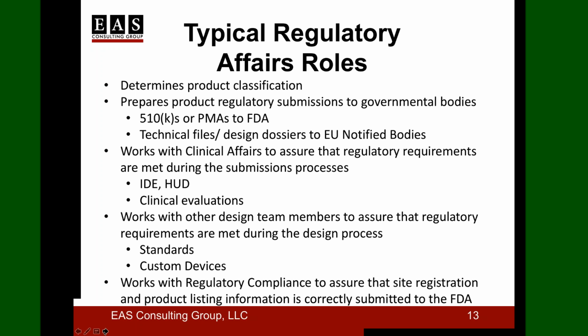On the side of the EU, it's called a technical file or design dossier. So you basically supply that paperwork either to the FDA or to a notified body, EU in this case, or other government bodies like Health Canada or whoever. Then you also work with clinical affairs. Those are basically the folks that are running these studies.